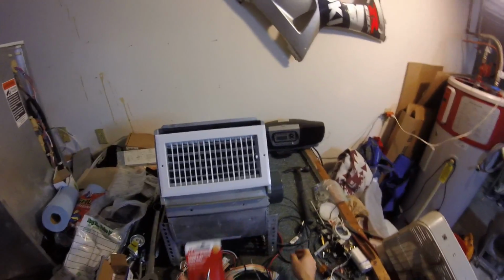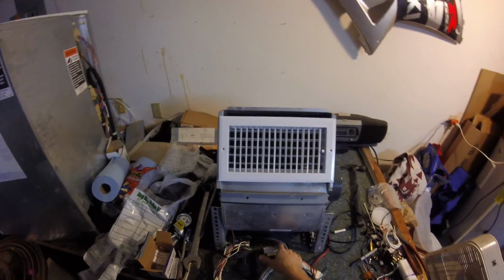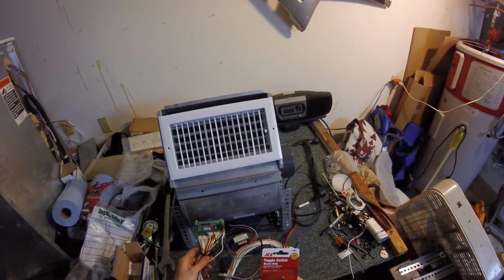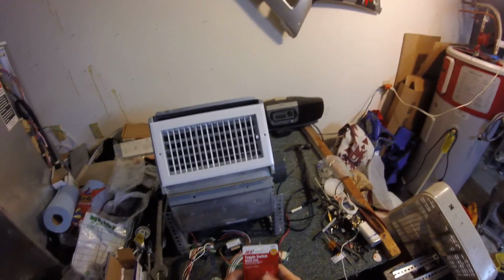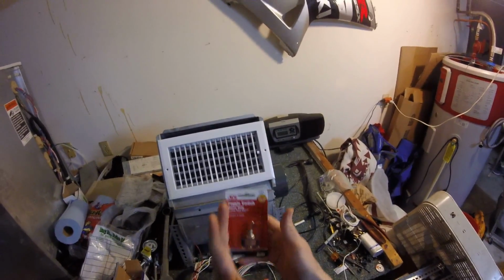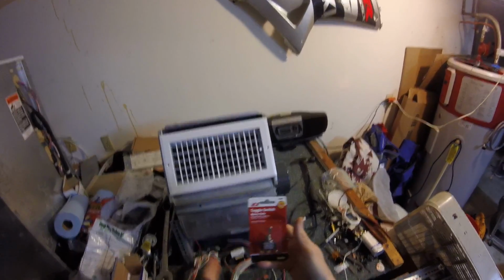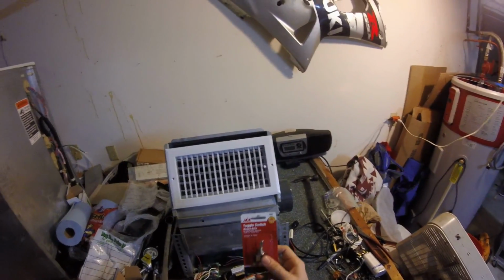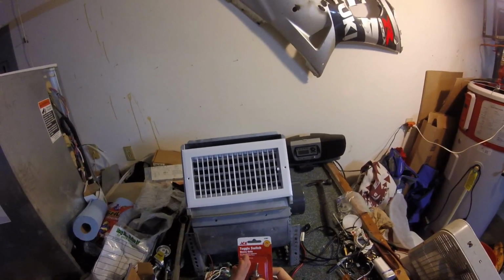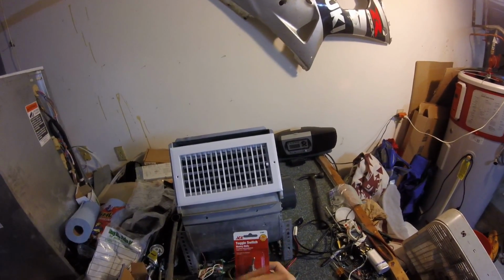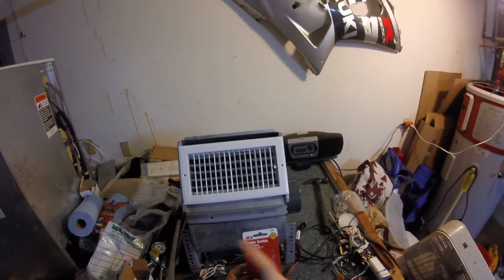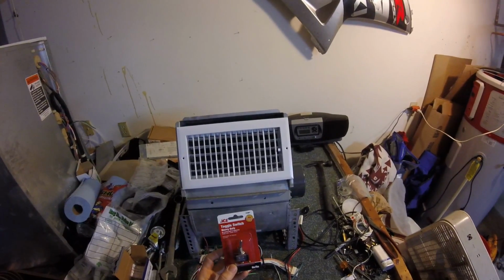This is going to be how we select 3 different speeds for the fan. The way I wire this: off, as soon as you plug it in, it's going to power the transformer up and energize the green speed, which will be low. So off on the switch is low. As soon as you plug the fan in, it's going to be a G call. We'll call that low, we'll call one set of contacts medium, and another set of contacts high.